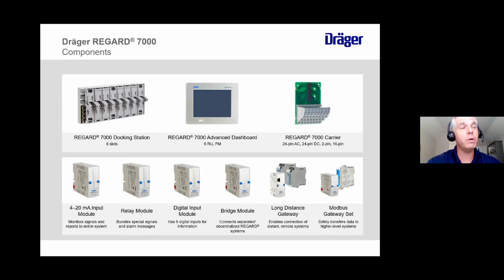Also we have carrier pins where you actually land your wires for that module. A really nice design feature of the Regard 7000 is that these carrier pins can go either above or below the docking station, depending on accessibility and ease of use, what the contractor wants to put in there, or the plant wants to put in there. Most folks will put all their pin carriers for the inputs on top and all their outputs for the modules on the bottom to keep them separated.